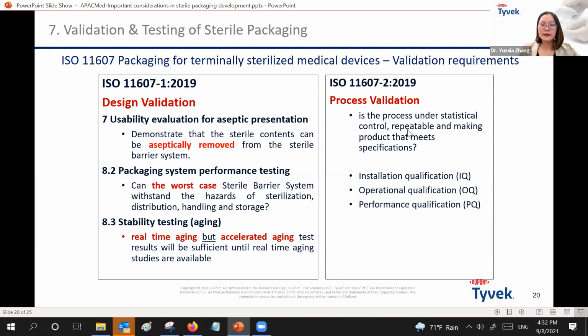And for the process validation, for example the sealing process validation, they normally involve IQ, installation qualification, OQ, operational qualification, and PQ, performance qualification, which should prove that the process can run under statistical control and produce repeatable results, making the products meet the specification.